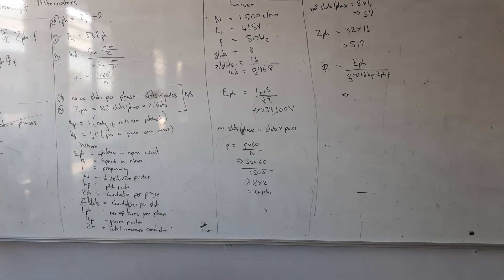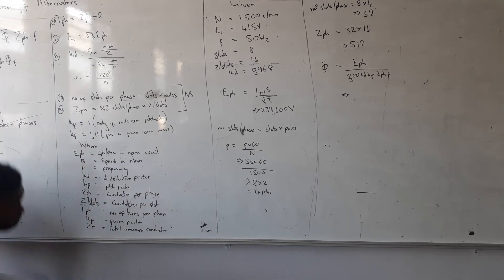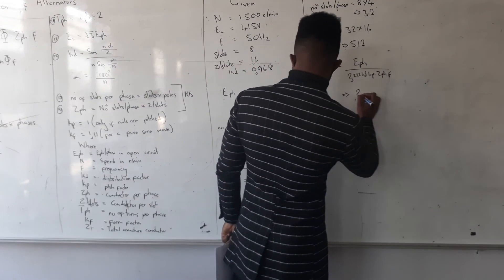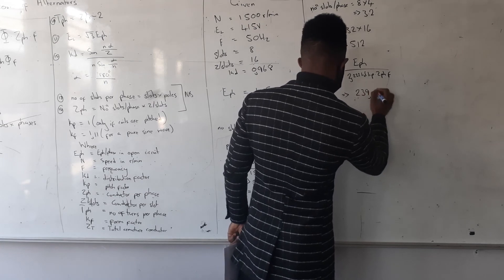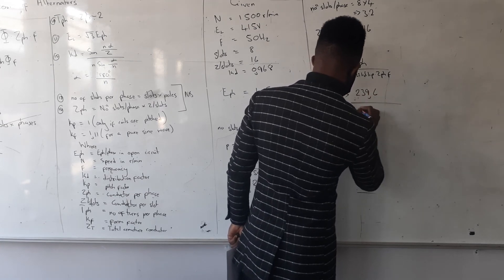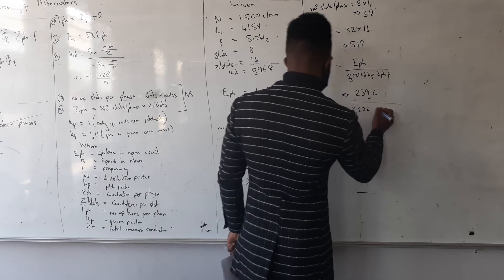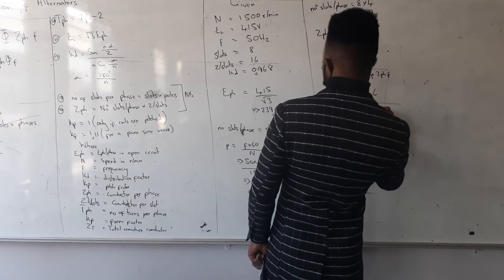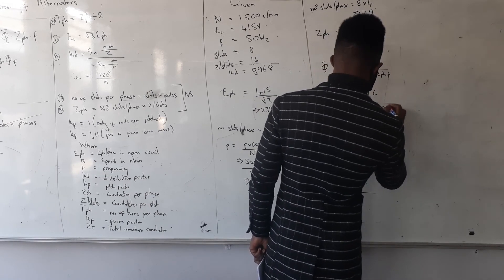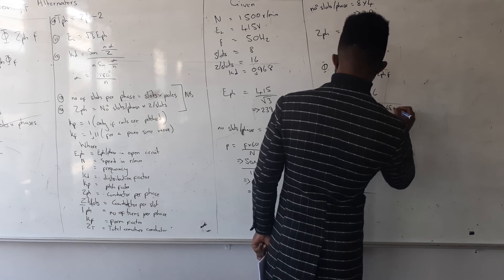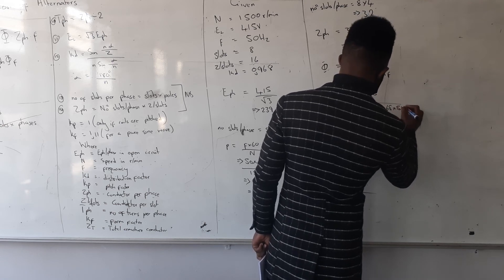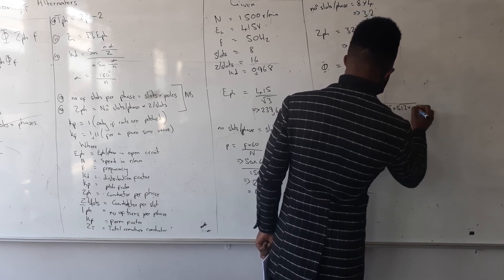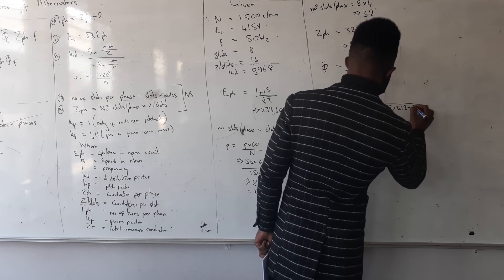Alright, so which means I'm going to also use my Kp as 1 because I'm not given Kp. My E phase is 239.6 divided by 4.44 multiplied by my Kd, which is 0.968, multiplied by Z phase, which is 512, multiplied by the frequency of 50.